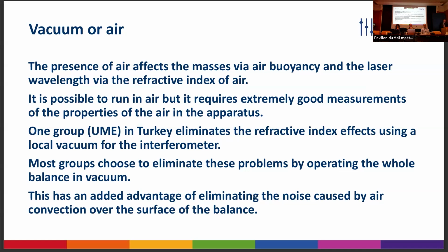But they then still have to measure the air buoyancy, but it's doable. Almost all the other groups choose to go into vacuum, which has a nice advantage of eliminating the noise caused by air circulation on the surface of the balance. It's a lovely thing to see all that vanish.